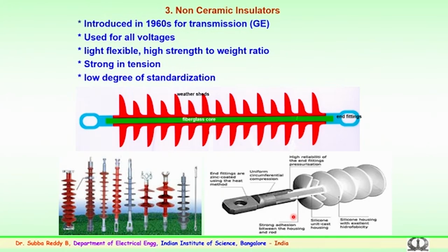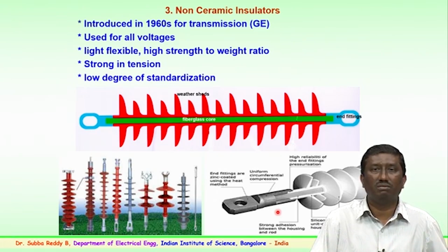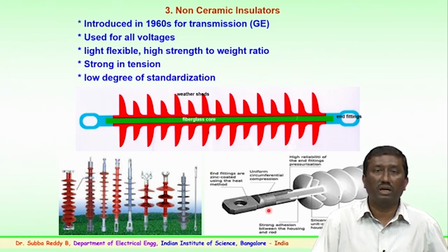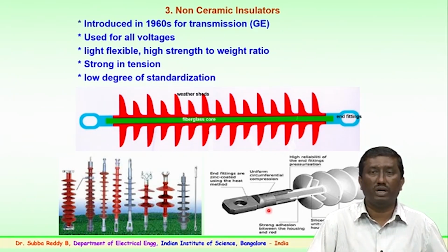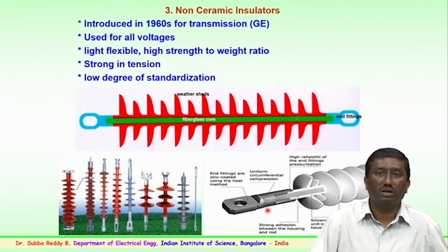So, the final or the recent origin is the non-ceramic insulator, or the polymer or composite or silicone rubber insulator, which are the terminologies being used. These non-ceramic insulators are of recent origin and advanced technology, particularly in the insulator field. These were introduced somewhere in the 1960s, initially for transmission, particularly by General Electric.